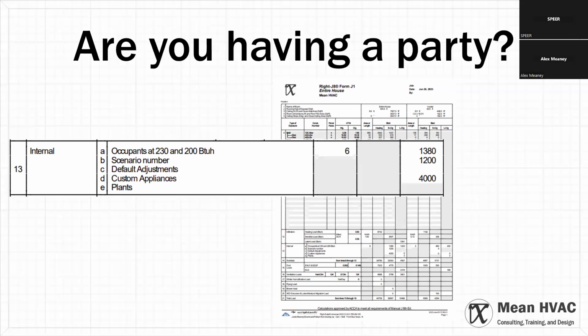Other software programs, specifically Elite, give you access to broken-down tables of individual appliances. Those are meant to have a run fraction associated with them. Some users will just spam every appliance, and before you know it, you've got 10,000 BTUs of appliance load. That's a pretty big no-no—though it can be an honest mistake. People count up the appliances in the home without realizing each one only runs a certain amount per hour, and you're supposed to adjust for that. So this is a common mistake, and a fairly common way people juice a load calculation.